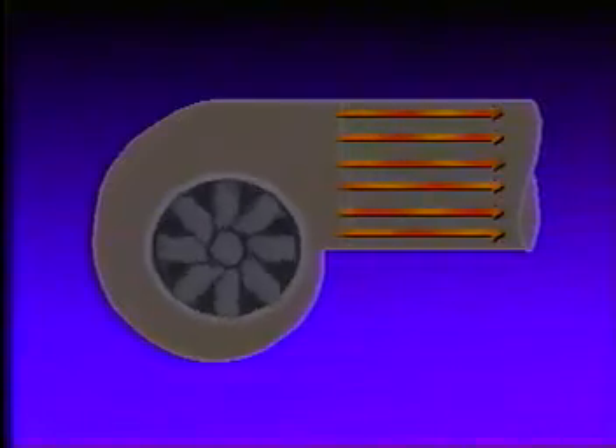Fans perform most efficiently when air flows straight into the fan and straight out of the fan. When air doesn't flow evenly into and out of the fan, performance drops. We call those performance drops system effects. The system is the path through which the air is pushed and pulled. Differing systems affect fan efficiency. If the fan can't run efficiently, operating costs can skyrocket.